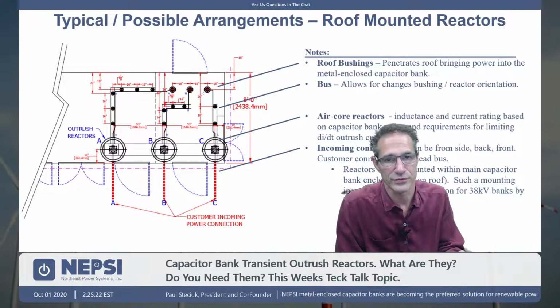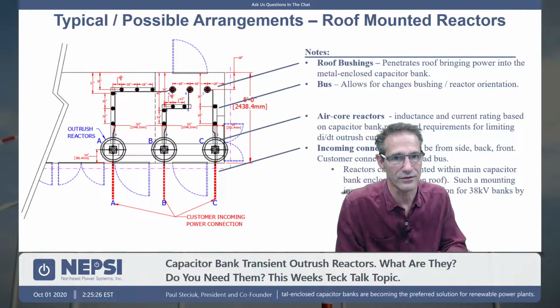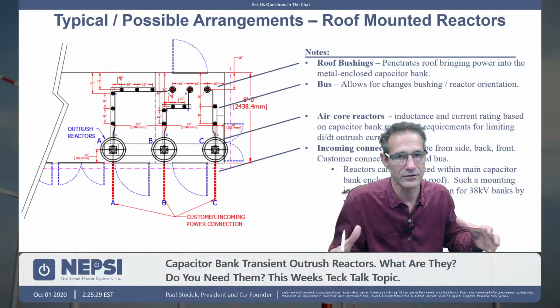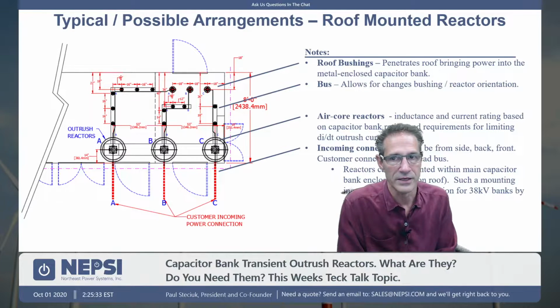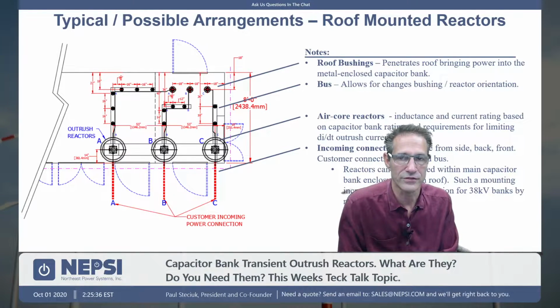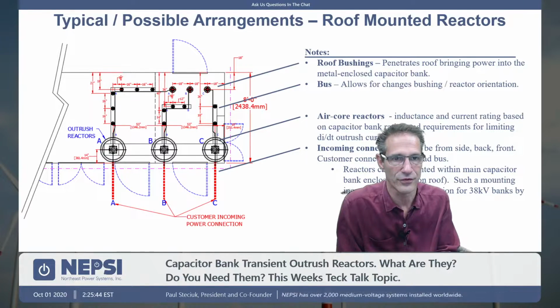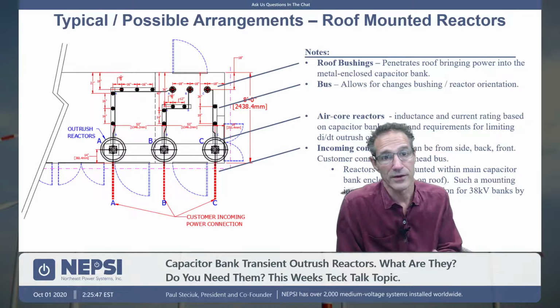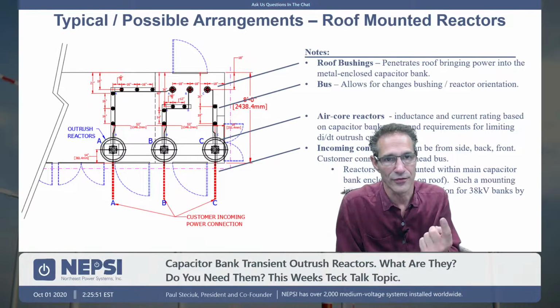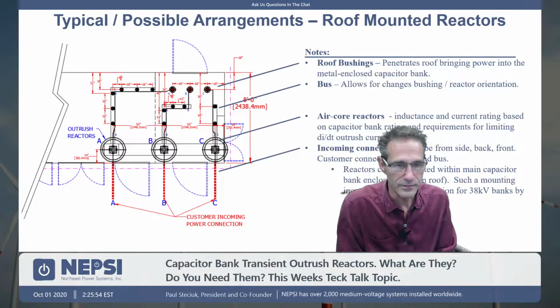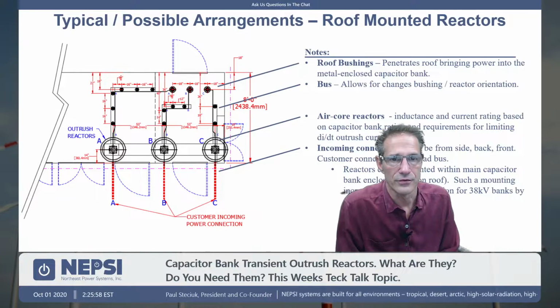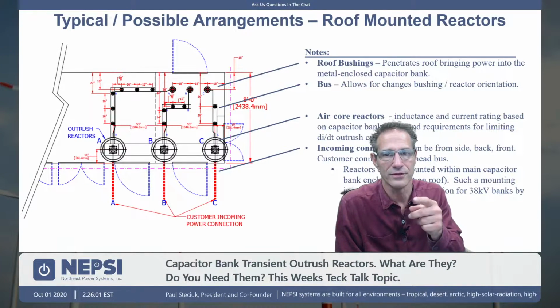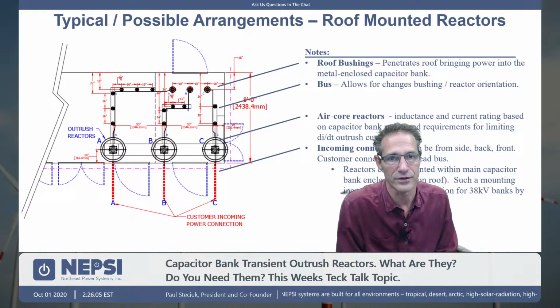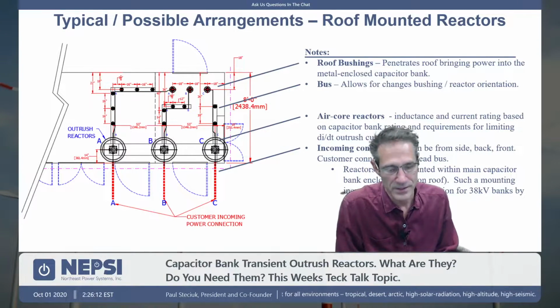If we're being asked to do outrush reactors, our first thought is, if we need inrush reactors, let's see what it's going to take to get to where we need to get to limit that outrush current to the correct value. In a spreadsheet tool that we have, we'll do that. You can put the inrush transient reactor values, the inductance, in there. Typically it is 50 microhenries for a 38 kV bank. That's the minimum. So you think about that for a three-stage bank, the equivalent inductance is one third of 50. So we're only at that point, or whatever the math is there. And that's really a small value in comparison to what we typically would see for an outrush reactor, which might be 200 microhenries in total. So very often we try to do the calculation, and the end result is we still have to put outrush reactors in. So good question, though.